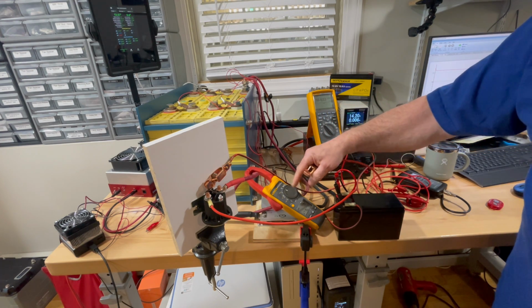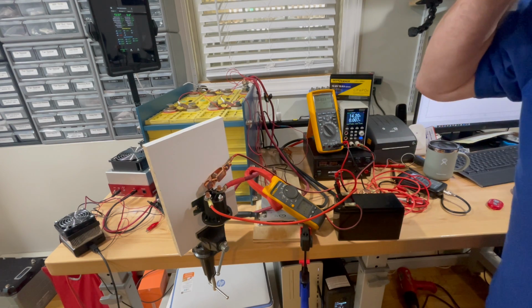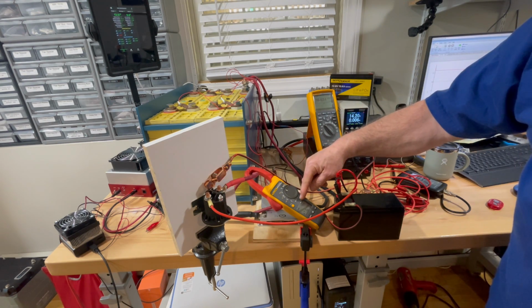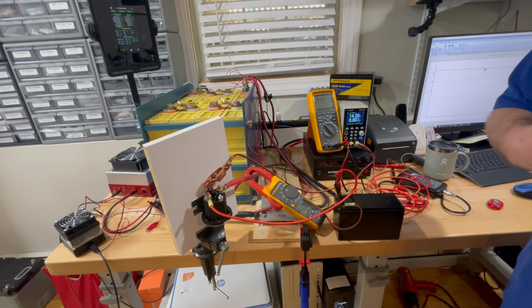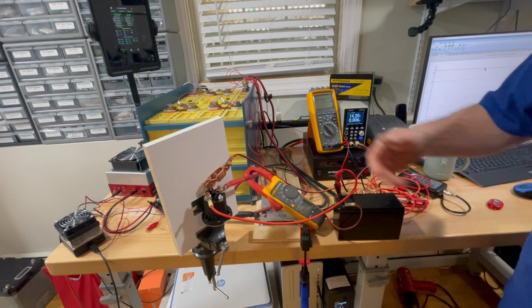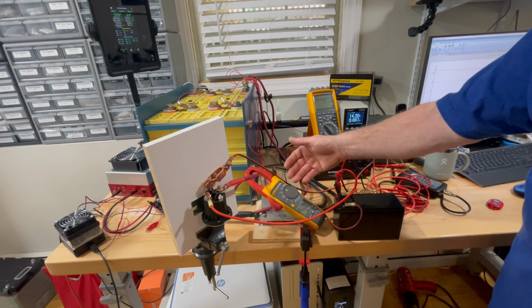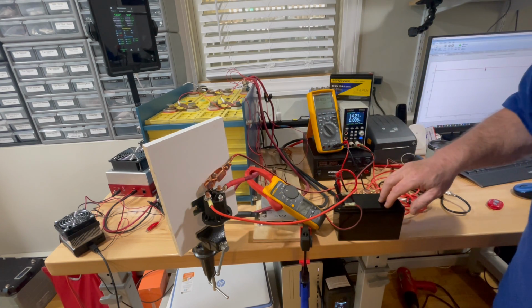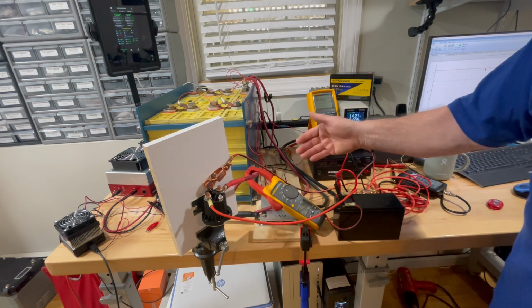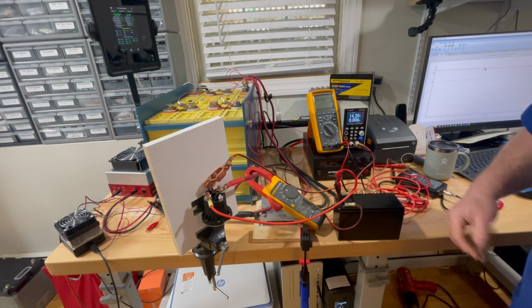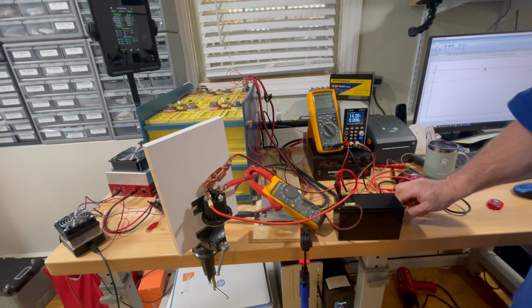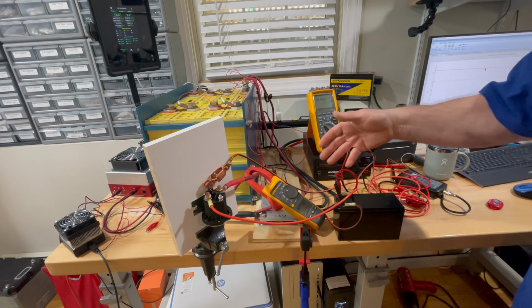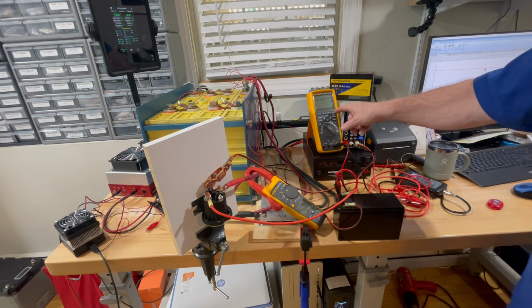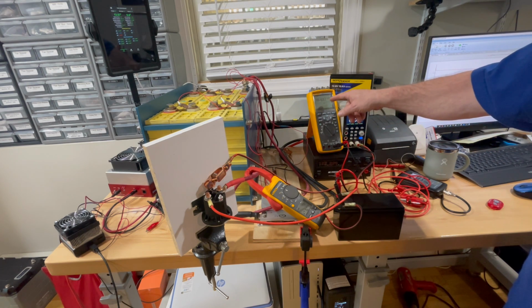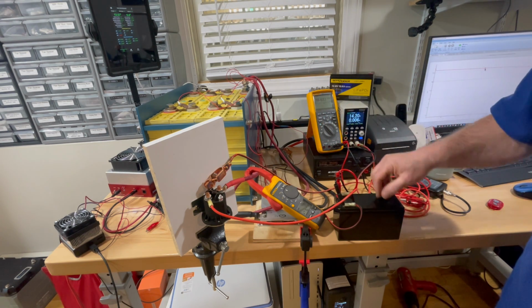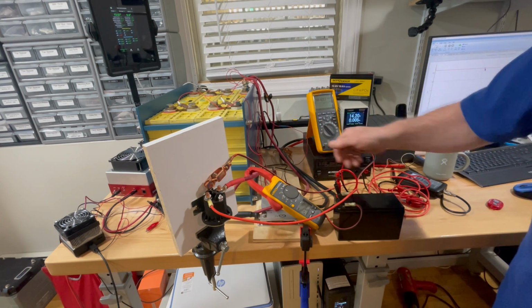The Fluke meter here is set to inrush. In terms of inrush meters, these are the only ones that we found that actually work and give a fairly accurate representation of inrush. We've tried Amprobe meters, which are also owned by Fluke. They don't work. We've tried Mastech, we've tried Uni-T, we've tried every other brand out there. None of them work for inrush. They claim inrush, but they don't work. The way that we test that is we use a shunt. We put this voltmeter across the shunt, and then we do the math. We can see the voltage drop across the shunt from the inrush, and that's how we calibrate our meters.